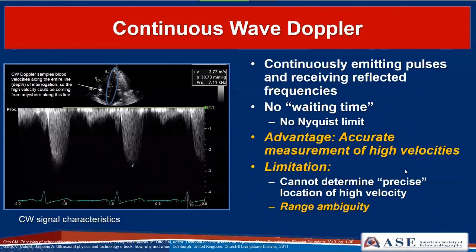With continuous wave Doppler, the transducer is continuously sending pulses and receiving reflected red blood cell frequency shifts. There is no wait time, so there is no Nyquist limit. The advantage is that it allows accurate measurement of high velocities. The limitation is range ambiguity—because we are constantly sending and receiving along the interrogation line, high velocities could come from anywhere in that path, so we cannot determine the precise location of the high velocity.